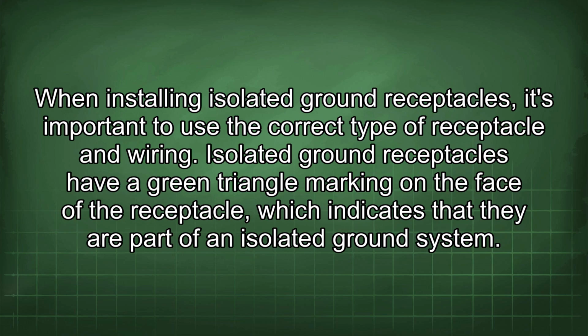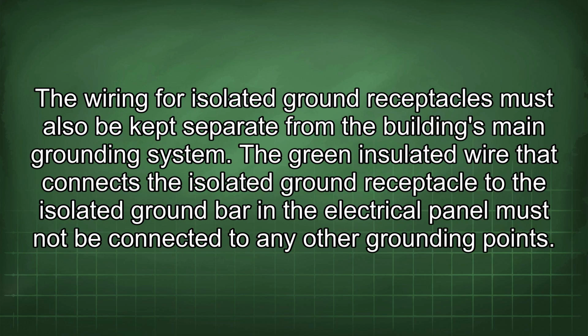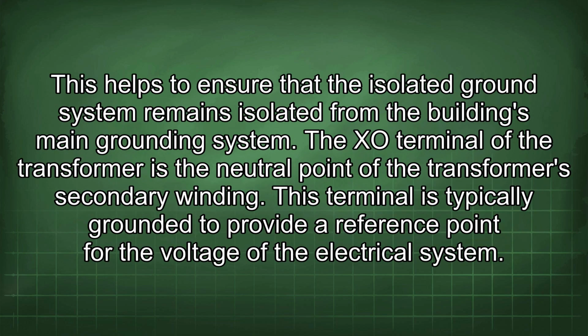When installing isolated ground receptacles, it's important to use the correct type of receptacle and wiring. Isolated ground receptacles have a green triangle marking on the face of the receptacle, which indicates that they are part of an isolated ground system. The wiring for isolated ground receptacles must also be kept separate from the building's main grounding system. The green insulated wire that connects the isolated ground receptacle to the isolated ground bar in the electrical panel must not be connected to any other grounding points. This helps to ensure that the isolated ground system remains isolated from the building's main grounding system.